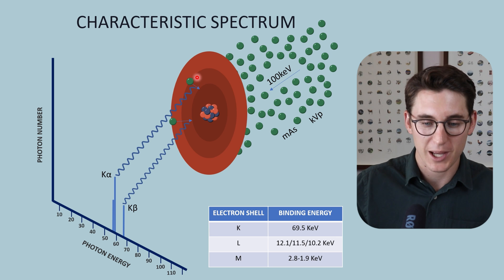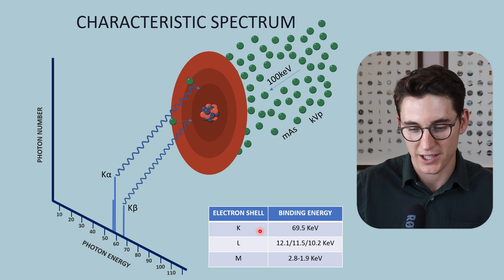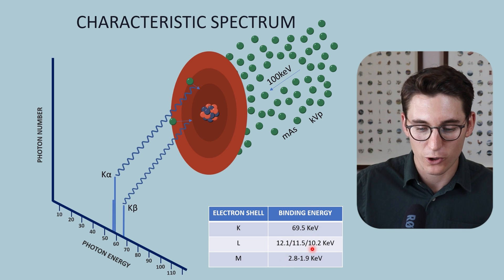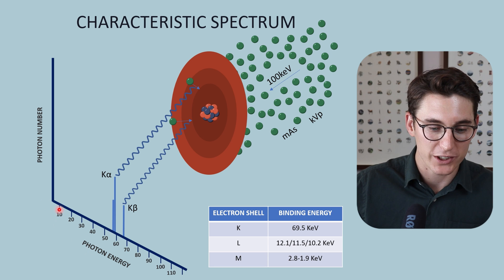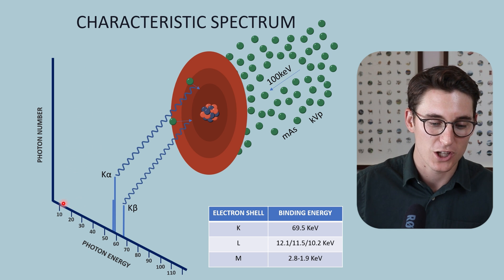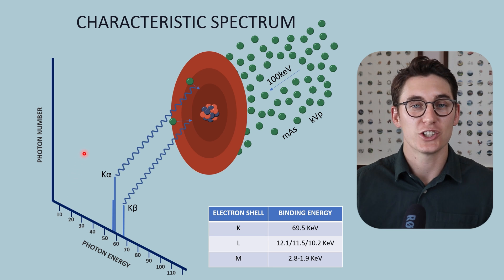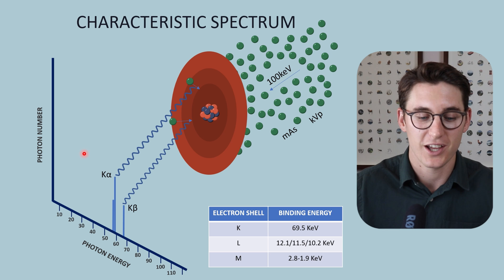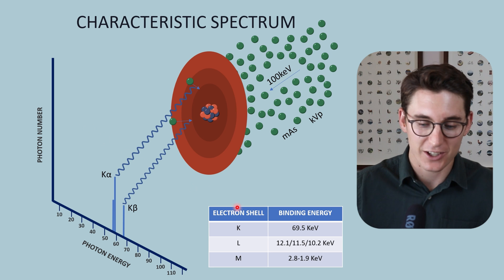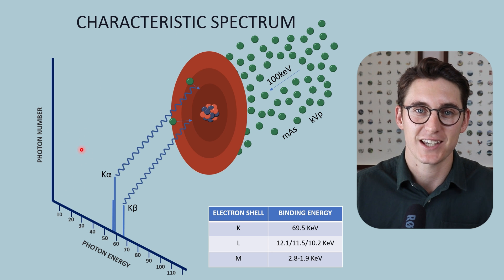You may be wondering what happens if an L-shell electron were displaced and an M-shell electron dropped in. In that case, we would be getting characteristic x-rays below 10 keV. We know that the inherent filtration will filter out those x-rays below 12 to 15 keV on our spectrum, just as we looked at in Bremsstrahlung radiation. And if we were to add added filtration, then none of those other characteristic x-rays would occur in our characteristic x-ray spectrum.